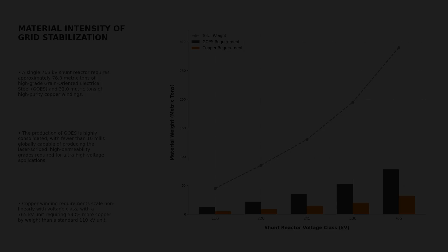This bottleneck is driven by extreme material intensity. A single 765 kilovolt shunt reactor requires 78 metric tons of laser-scribed grain-oriented electrical steel and 32 metric tons of high-purity copper. The production of this specialized steel is highly consolidated. Fewer than 10 mills globally can produce the grades required to minimize core losses.